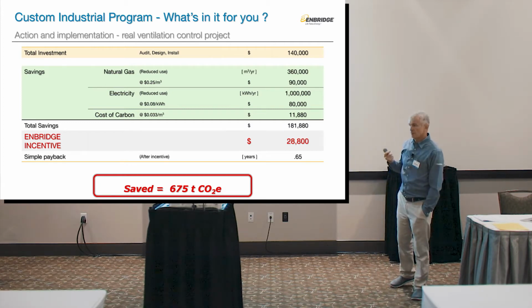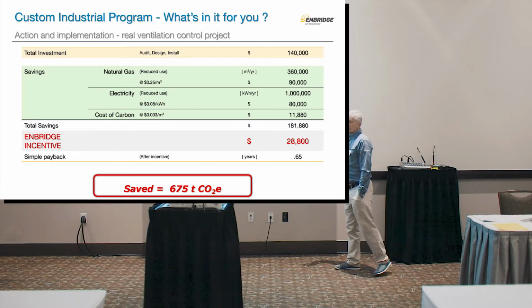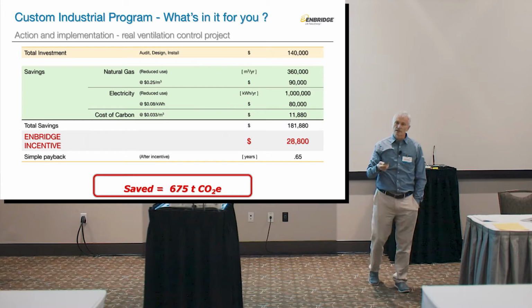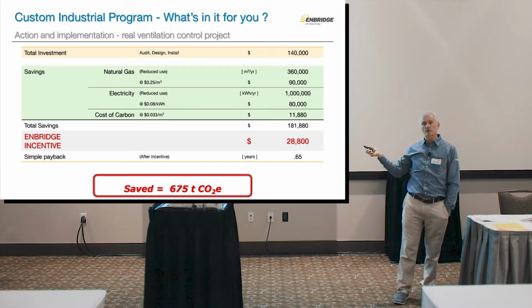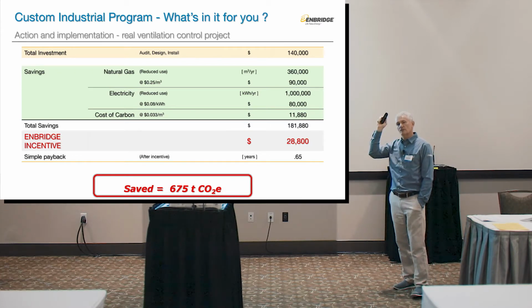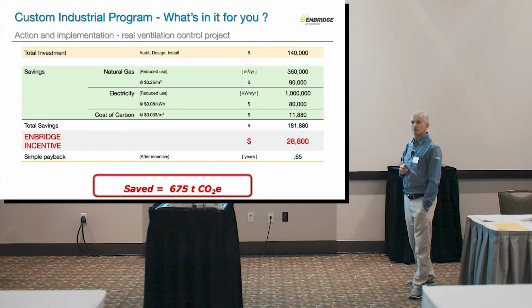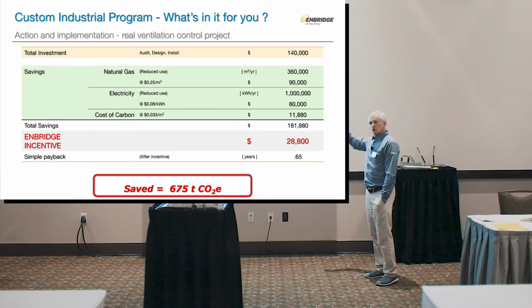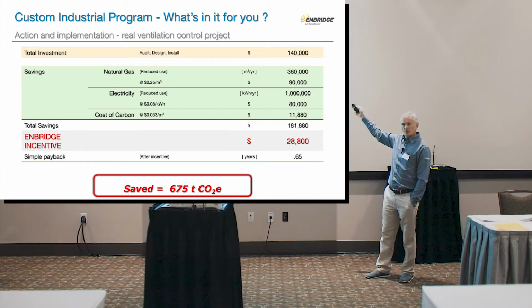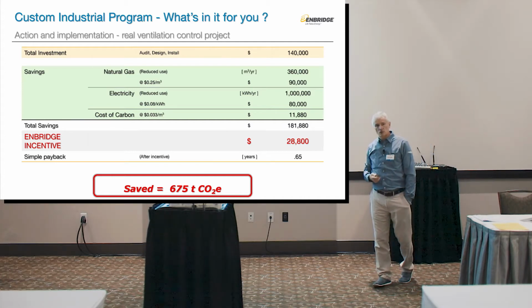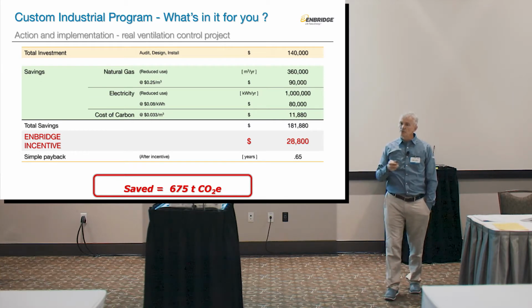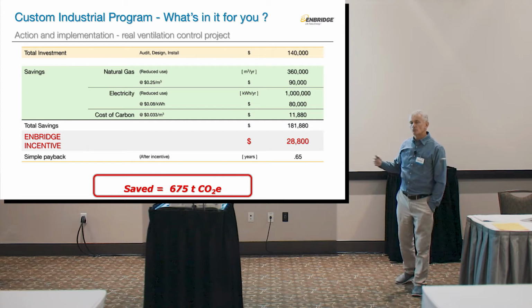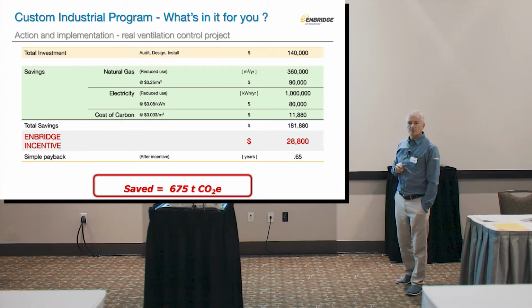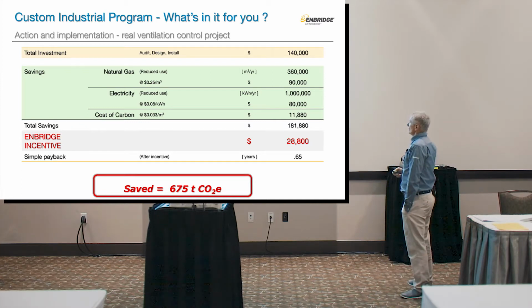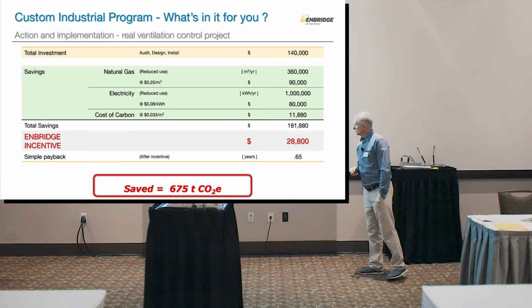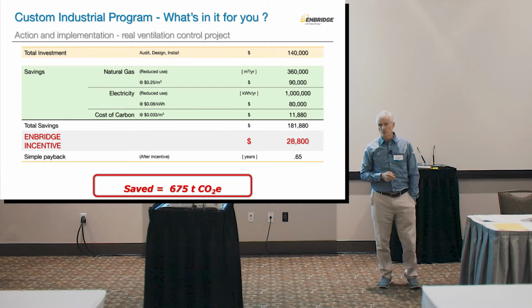They managed to save $181,000 in year one. I have an email from the customer later telling me that he's afraid that he set the bar too high. They actually implemented this system, but for the summer mode, for air conditioning, down in their facility in North Carolina, the year after. No specialty trades, no big projects, no big vendors, simple installation. And of course, because it was a unionized environment, we gave the union the job to pull all the wires between the units, so nobody complained about having the vendors do the programming. If anybody cares, that was the savings, 675 tons of CO2 equivalent by doing that project.